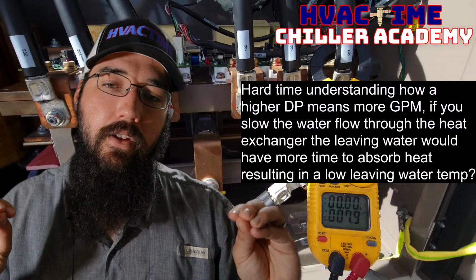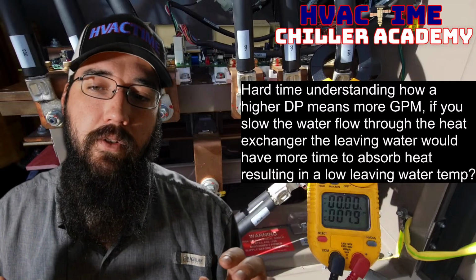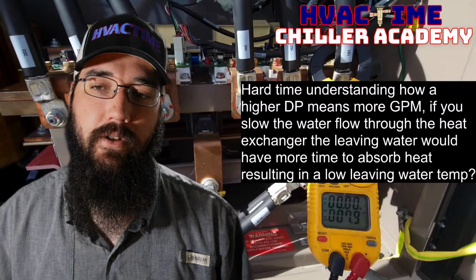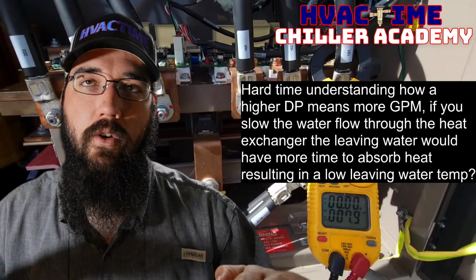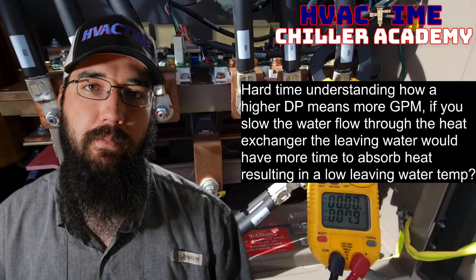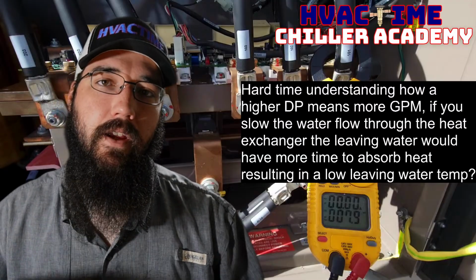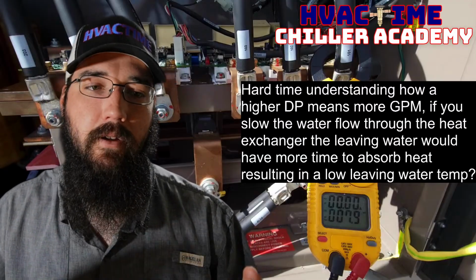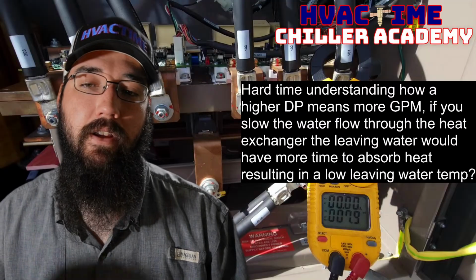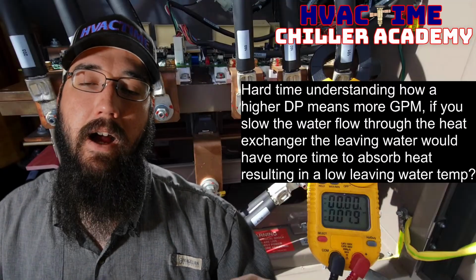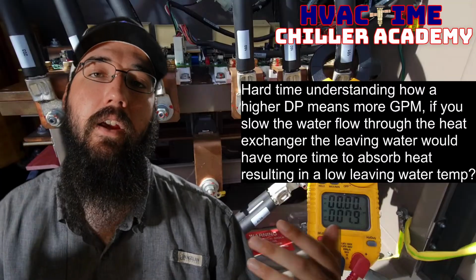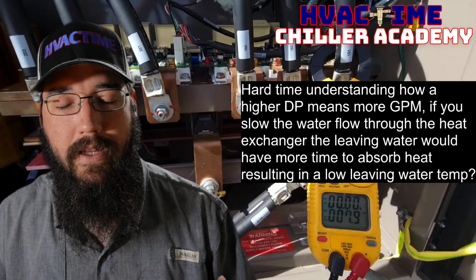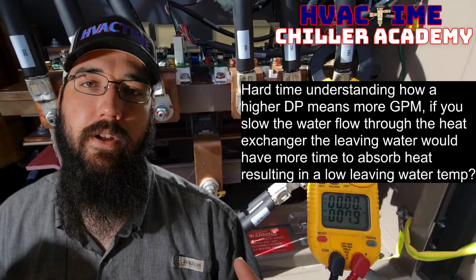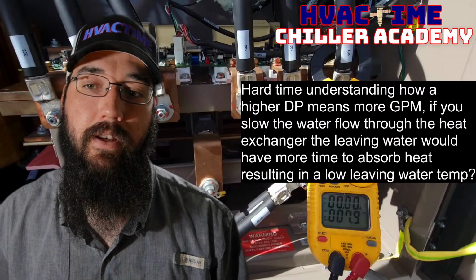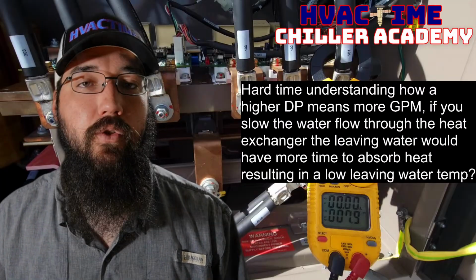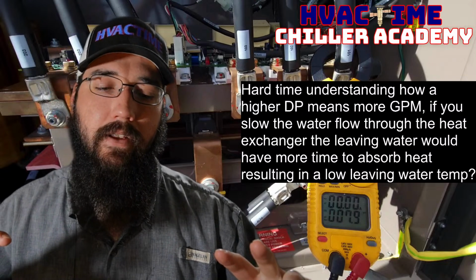Anyway, so in terms of TD, temperature difference, if we slow down the GPM, or lower the GPM, then yes, we will end up having a higher TD, because we can pull heat out of the water easier, which makes it easier to hit leaving water set point, and it's something we have to be careful with. And I do just want to hit on this again, that there is a difference.